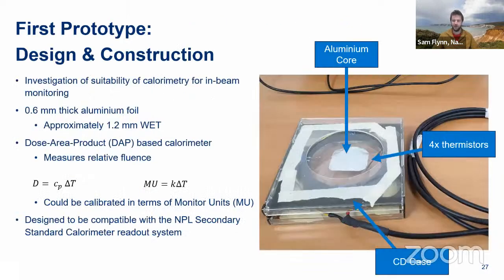So I am so proud of this instrument, and I love to show it to everyone I can, but this is the first transmission calorimeter we built. It is using supermarket aluminium foil as its sensitive core region, and it's held in a CD case, which I bought from a charity shop on the high street. It's using polystyrene film to enclose the air within it, and this aluminium core is held in the air using 4 thermistors. The tension from the wire of the thermistors is what thermally isolates it from the environment. This is measured to be about 0.6 millimeters thick, which is about 1.2 millimeters water equivalent thickness. So it satisfies that requirement for a monitor chamber.